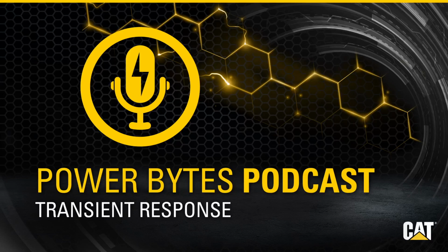Thank you, Lou. It's great to be back with you. Bryan, can you help us define what a transient is on a genset? Yeah, whenever there's a sudden change in the load supported by the genset, the frequency or the voltage of the generator is likely to be impacted for a temporary period. This change from steady state operation is considered a transient.